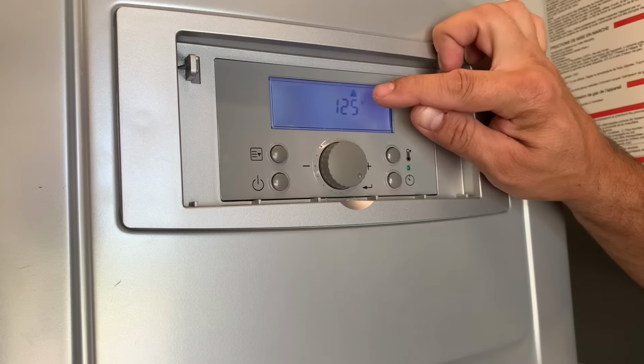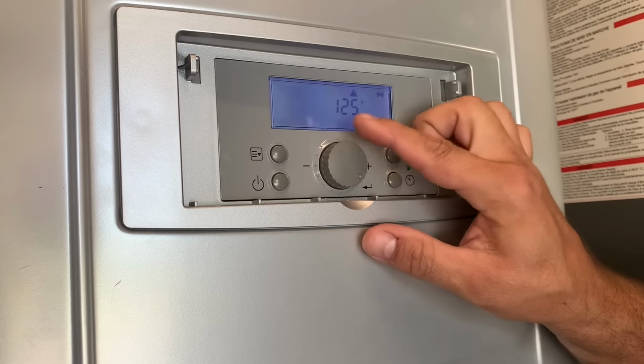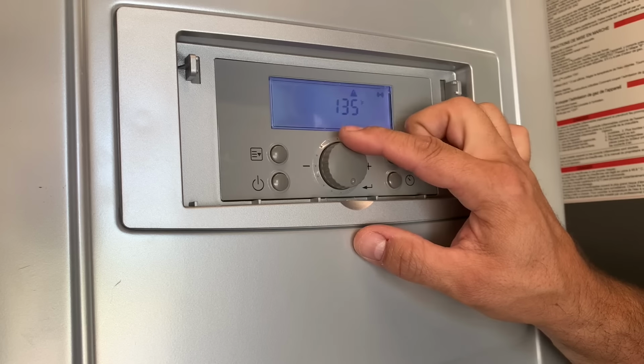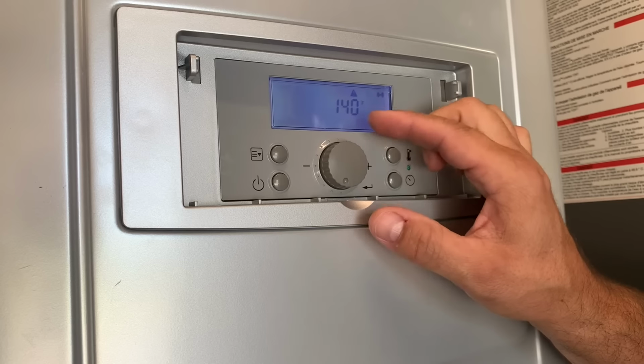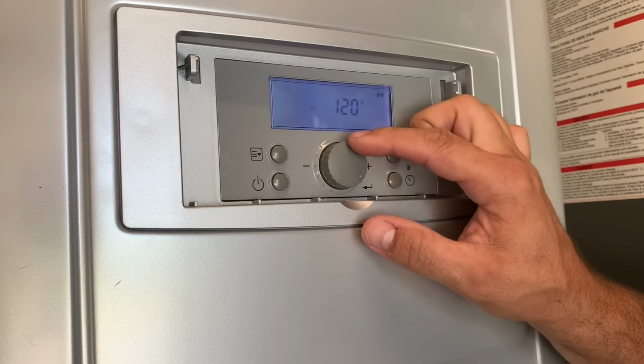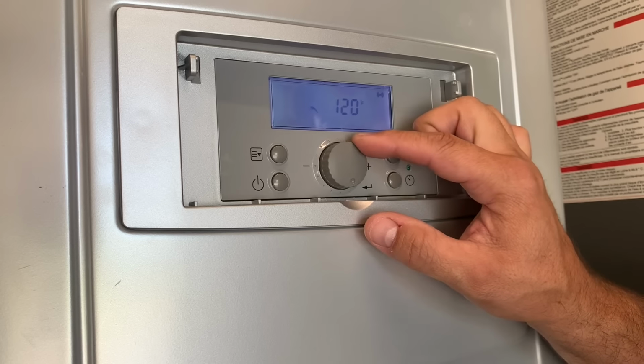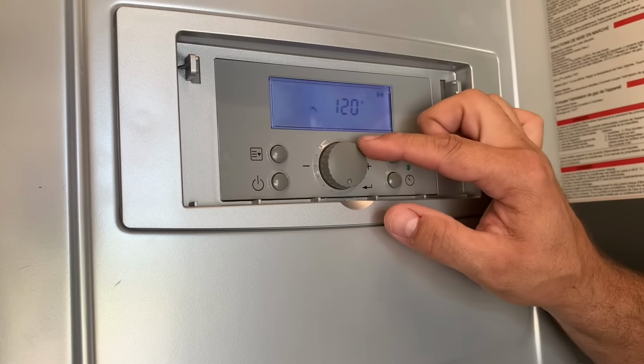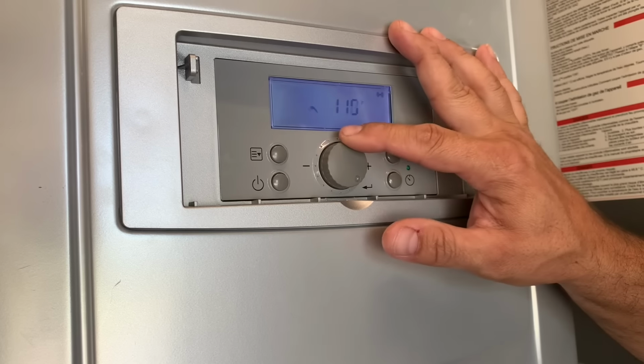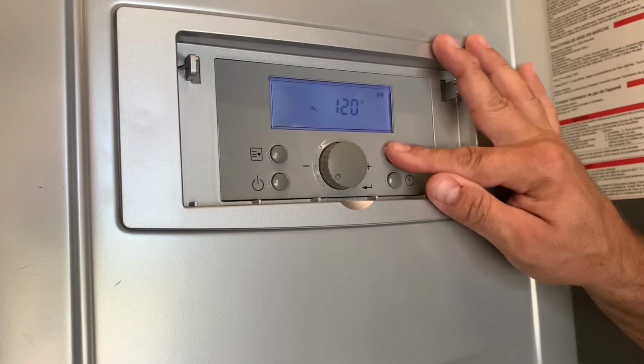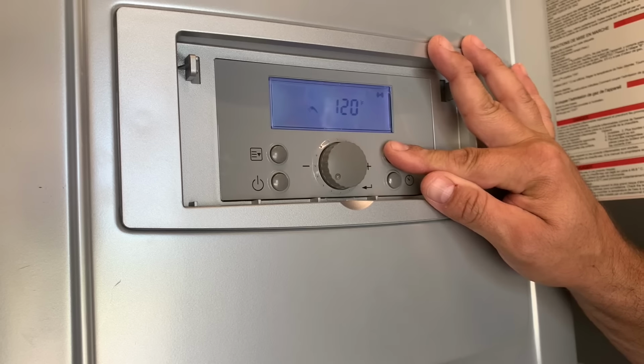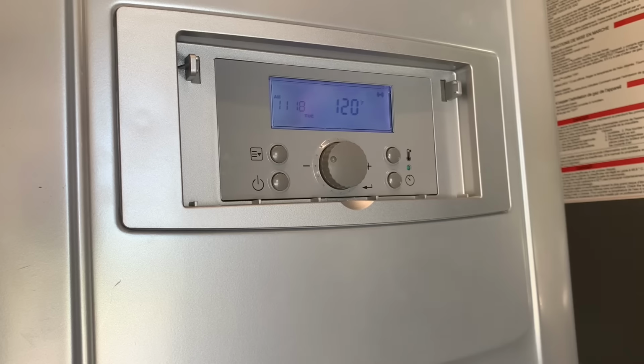Okay, now we've got the icon for the high temperature warning and it sits at 125. We can go up at 5-degree increments to 140. If you go below the 125 back to 120, it just resets to the standard 100 to 120. Okay, well we want to go above 120, so we're going to hold this down again, and nothing happened.